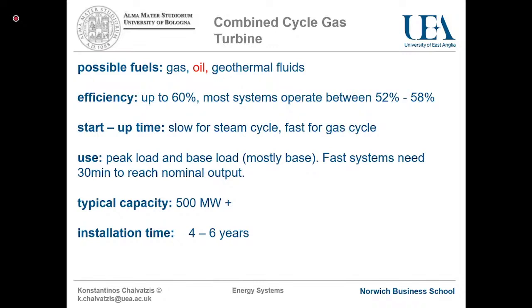Startup time depends now. If you have independent cycles, so the system doesn't run on the same shaft and there are independent shafts and independent generators, then you can have a fast gas cycle and a slow steam cycle, and you can combine them in whatever way makes sense. In most cases, they're single shafts, so really it's not that fast to catch up, it's still base load systems. So it depends, like I'm saying here, your fast systems need at least 30 minutes to reach nominal output. Typical capacity, they're not small. These power stations typically tend to be around 500 megawatts, exactly because they have the two turbines, so they're usually of significant power output. Installation time is 4 to 6 years, but again depends on regulatory stuff and what kind of delays might occur. But 4 to 6 years is quite standard for these.